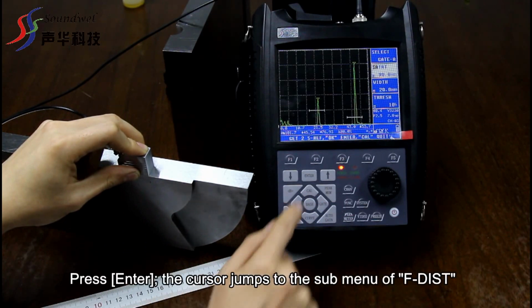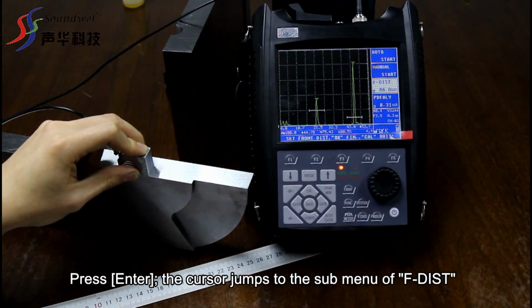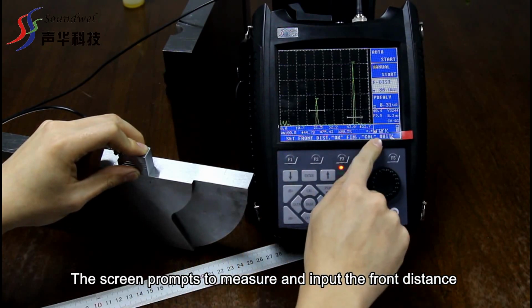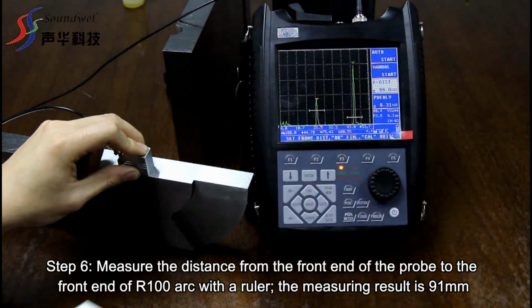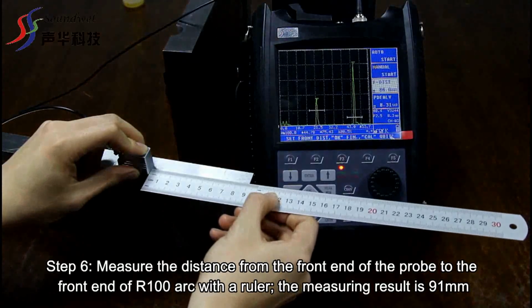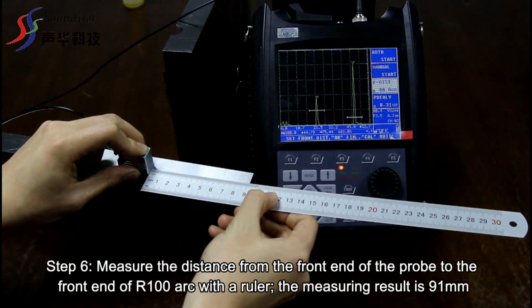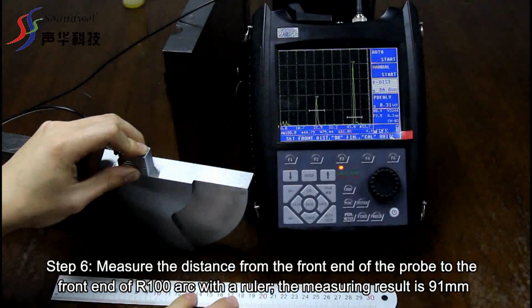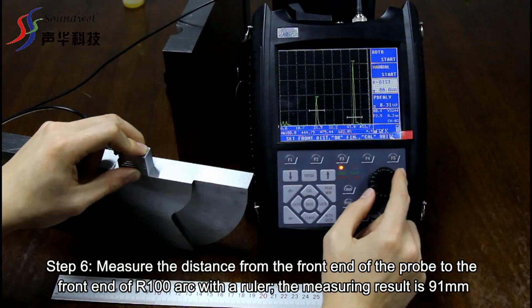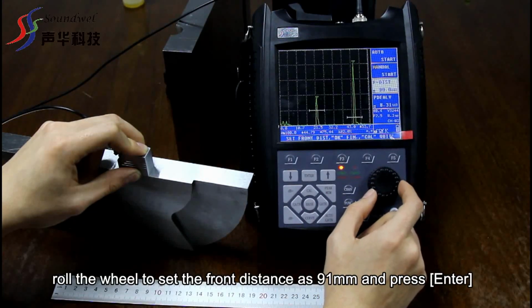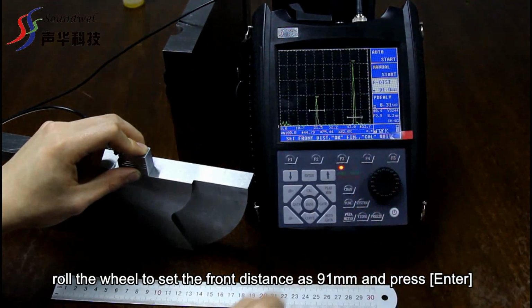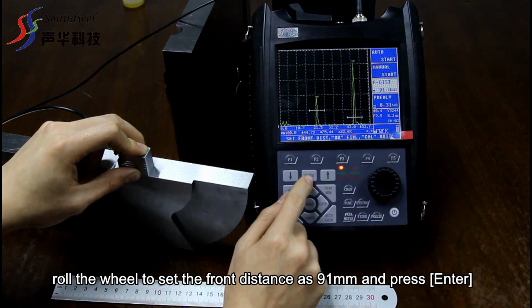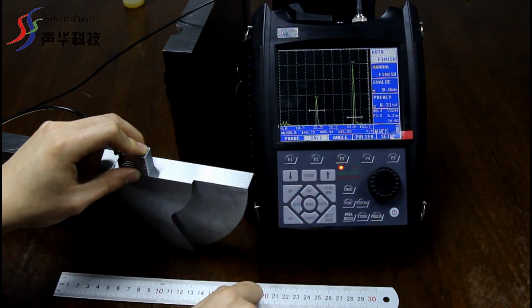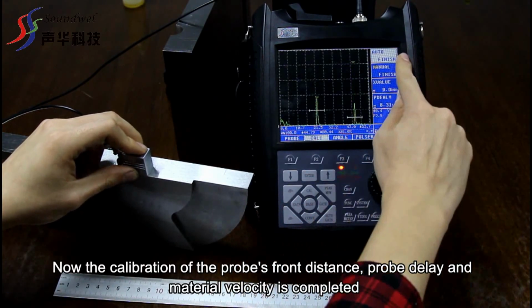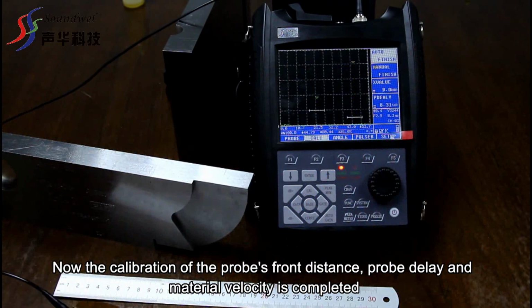Press Enter. The cursor jumps to the submenu of F-dist. The screen prompts to measure and input the front distance. Step 6. Measure the distance from the front end of the probe to the front end of R100 arc with a ruler. The measuring result is 91 millimeters. Roll the wheel to set the front distance as 91 millimeters and press Enter. Now, the calibration of the probe's front distance, probe delay, and material velocity is completed.